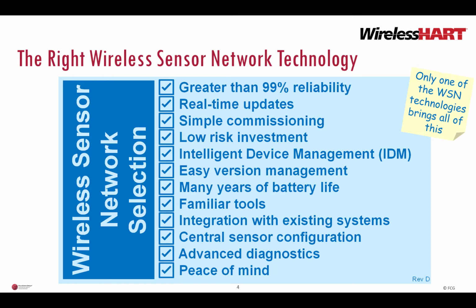It can use the same intelligent device management software as wired instrumentation if you like. Has long battery life. You can use the same field communicator as wired instrumentation. Data integrates with your existing DCS, PLC, historian, and other software. You can centrally configure sensors. You can access advanced diagnostics like vibration spectrums. But wireless sensor network technologies are not the same. There are very significant differences between them. Only one of the technologies offer these benefits. Some technologies have none of these benefits.